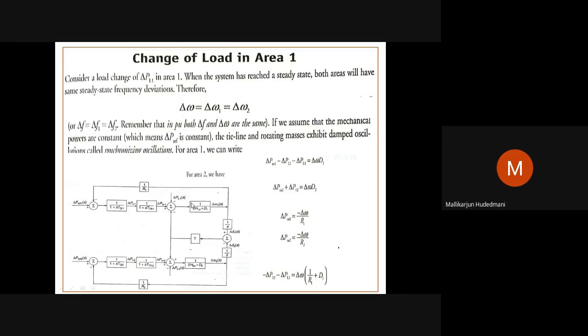See here, load changes in area 1. Area 1 has to respond actually, but the frequency deviation of this interconnected system is common to the controller of this and common to the controller of this. Therefore, this deviation delta omega is the reason that the governor will act and make a mechanical supplement here. Similarly, this frequency deviation is common to area 2's governors also. This is also going to reflect delta PM2. See the beauty of this. Area 1 is far away, kilometers or hundreds of kilometers far away, and this is also far away from that. Change of this is addressed by this, and change of this is addressed by this other way also when I look the other way. Therefore, delta PM2 is minus delta omega by R2.